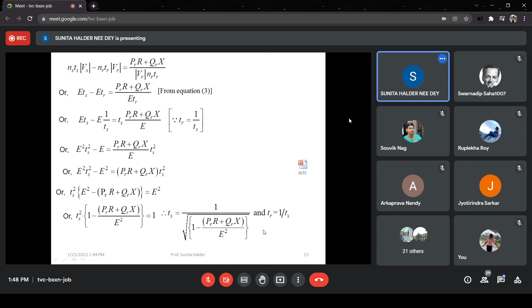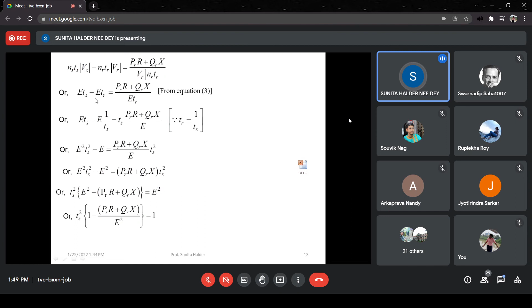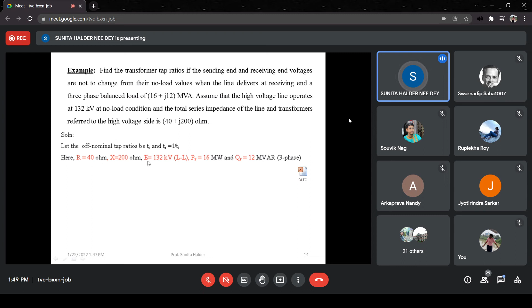Now, if I give an example, it may be more clear to you. We have to find out the transformer tap ratios, obviously for OLTC, if the sending and receiving end voltage is not to change from its no load value, when the line delivers at the receiving end a three-phase balanced load. That means whatever be the no load voltage setting, that will be there. But the load has been changed to 16 plus j12. So actually E is the no load voltage value. Here all the things are given: R, X, E, P, Q. Just put the expression and find out T and then find out Ts.